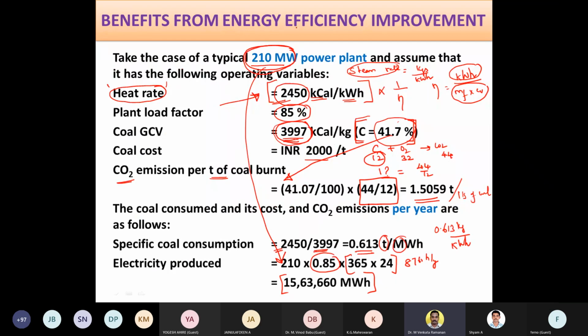These two pieces of information were already available: 2450 kilocalories per unit of electricity is the heat rate that has to be supplied, and the calorific value available with the coal was approximately 4000. So if I burn 1 kg of coal, it would give me 4000 kilocalories of heat.